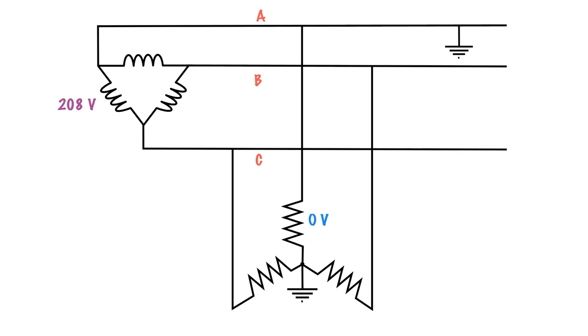But there's another issue that's at hand here, is that I now have this resistor still gets voltage. They aren't going to stay the same brightness, because what's going to happen here is this ground point here is the same potential as up here, which means that this ground point here is the same potential as line A. If I go on my delta system C to A, I'm going to get 208 volts. Down here, C to A, I'm going to get 208 volts. Same thing over here, B to A, if I did it line here to line here, typically I would get 208 volts. Well, it's the same thing here, because this has become A as well, so I'm going to get 208 volts on that one.